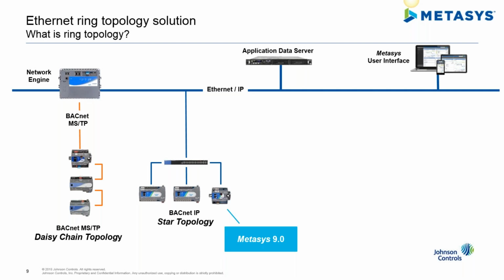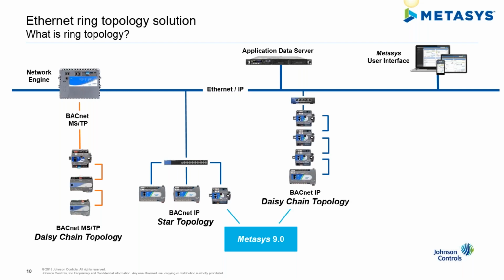And at Release 9, our IP controllers supported being networked together using a star topology, shown here, where you home run the Cat6 cabling from each controller to a switch port. And then we also supported at Release 9 a daisy chain topology, where the Ethernet cabling is run from controller to controller and up to the switch port and only uses one switch port. So each of these two topologies has its own associated pros and cons.